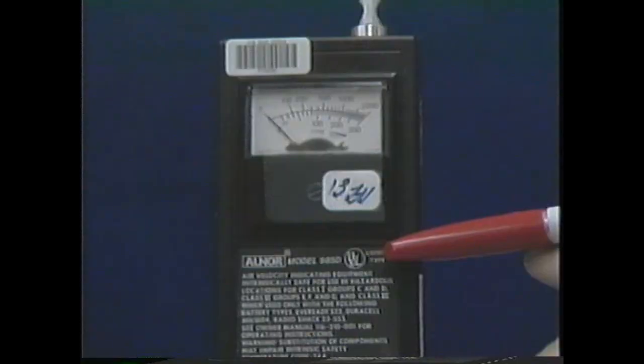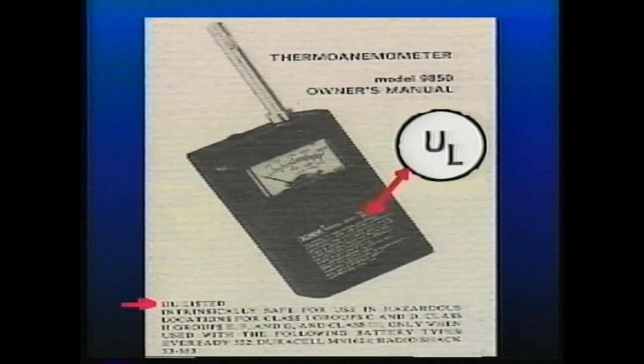The accuracy of this device is stated on page 10 of the owner's manual, along with other specification information. The accuracy is plus or minus 3% of the reading and plus or minus 1% of full scale. Now see the UL listing on the cover of the device and also on the instruction manual. Note that the unit is intrinsically safe, but only in certain locations as specified. This is critical to safe operation and must be considered before using the velometer in any environment to prevent creating a hazard.